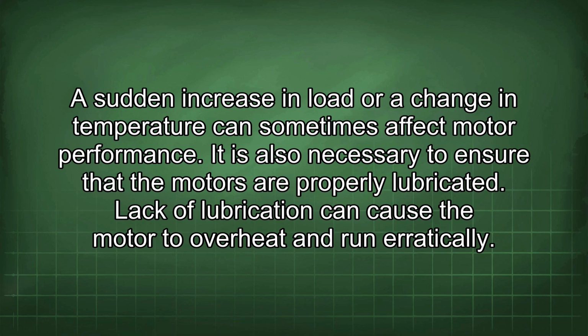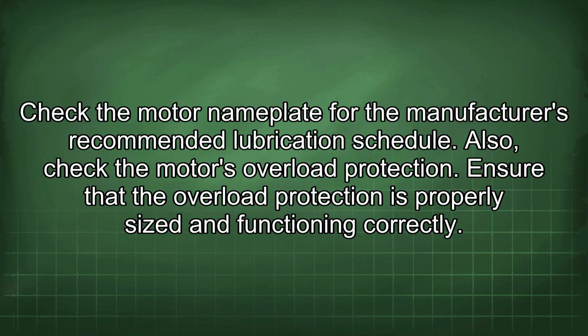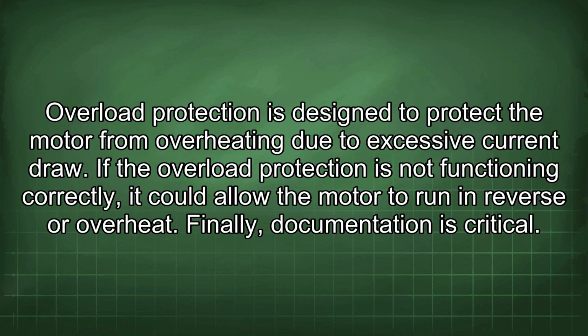It is also necessary to ensure that the motors are properly lubricated. Lack of lubrication can cause the motor to overheat and run erratically. Check the motor nameplate for the manufacturer's recommended lubrication schedule. Also, check the motor's overload protection. Ensure that the overload protection is properly sized and functioning correctly. Overload protection is designed to protect the motor from overheating due to excessive current draw. If the overload protection is not functioning correctly, it could allow the motor to run in reverse or overheat.